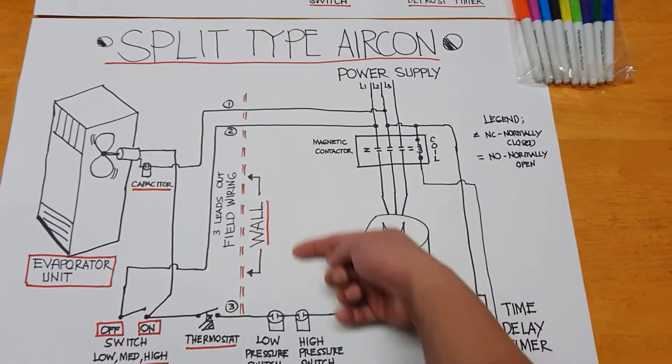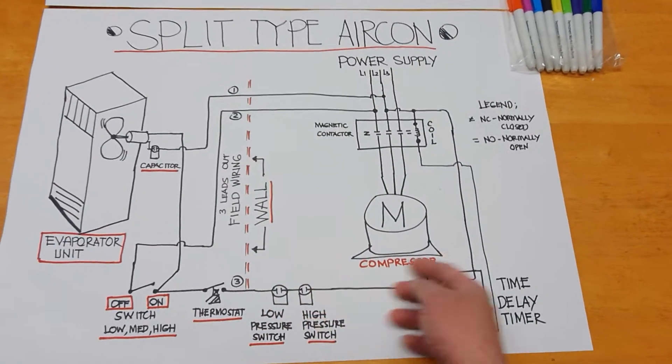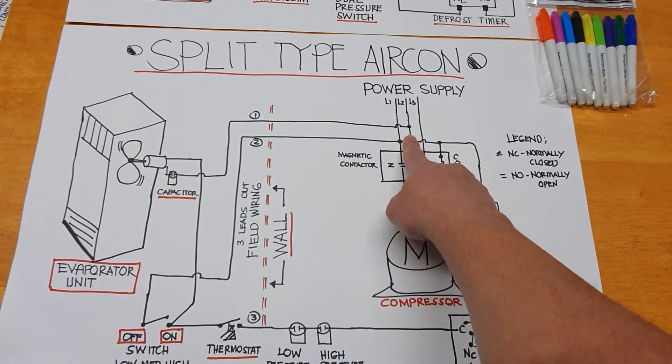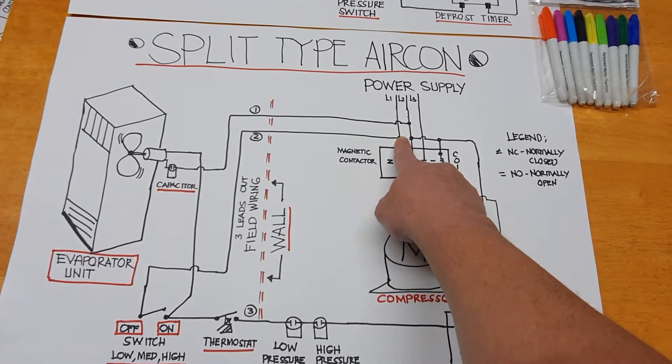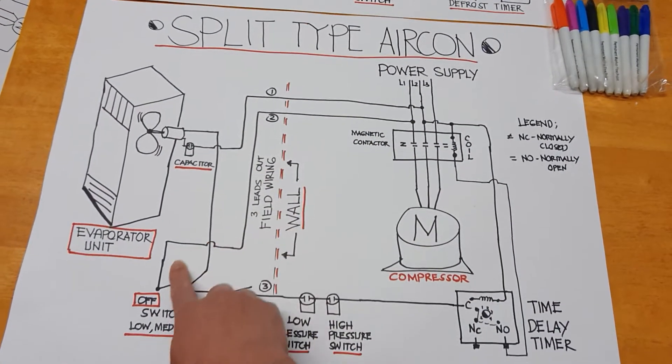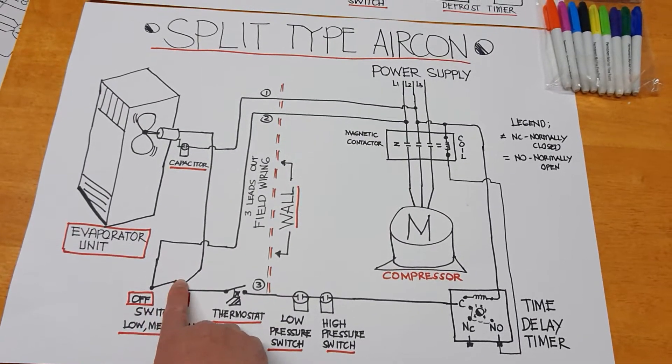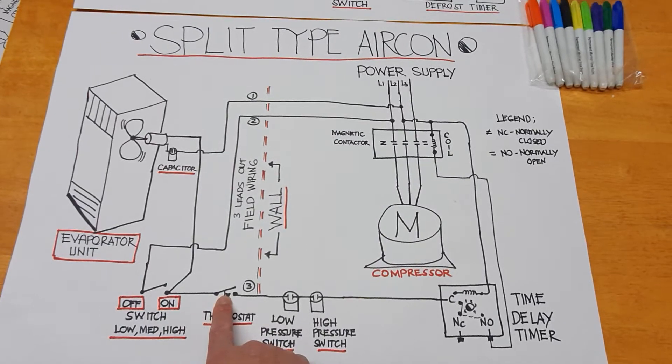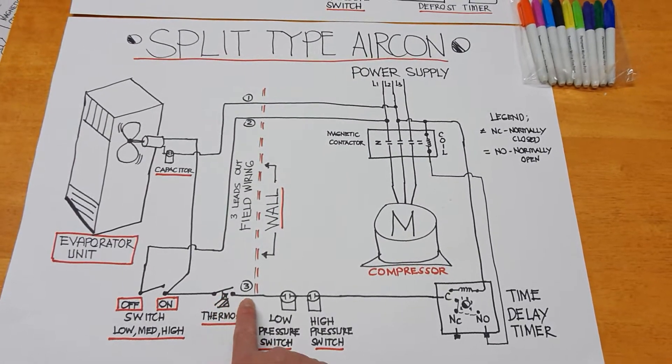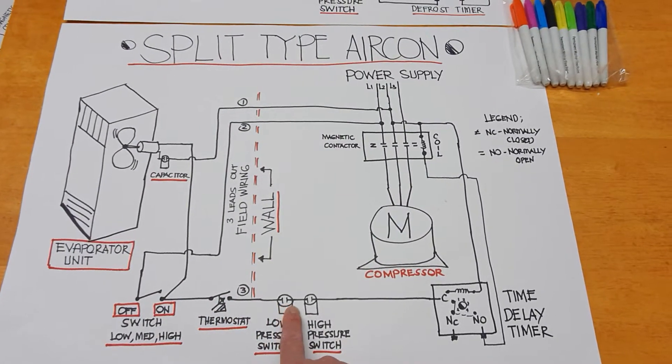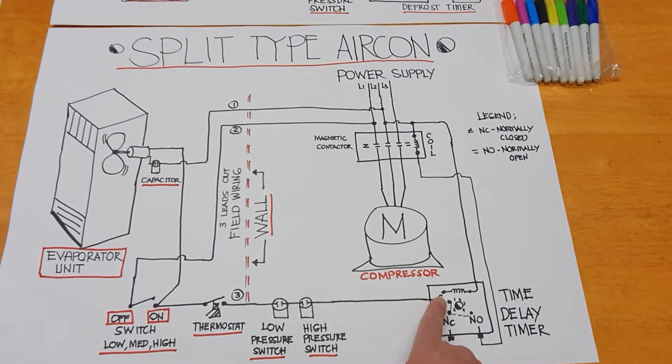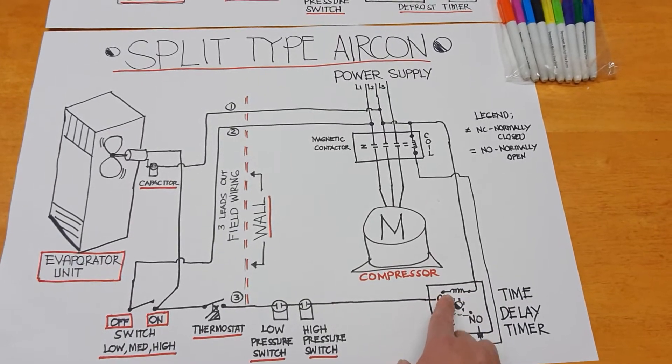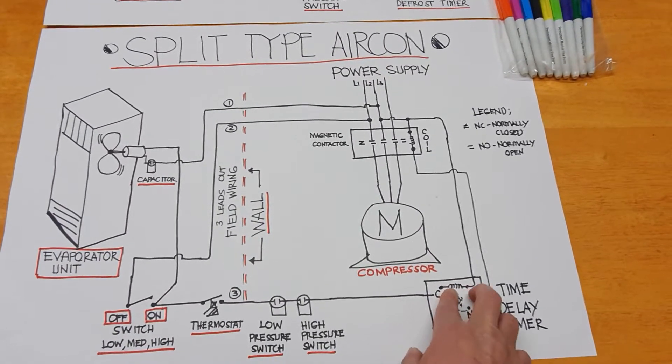So this is the connection I will explain it to you. Now line one will go to the switch. When you turn this on, the power will go straight here through the thermostat, low pressure switch, high pressure switch, and then it will go to the commons of time delay timer. So this is the coil of the time delay timer once supplied.